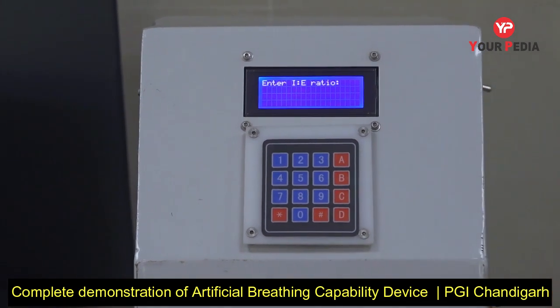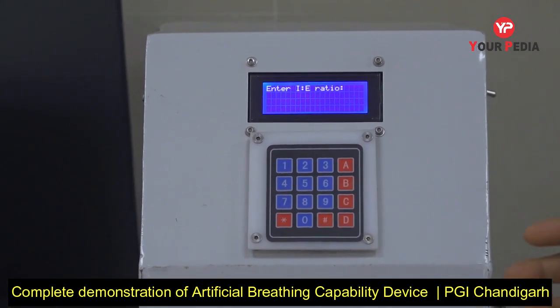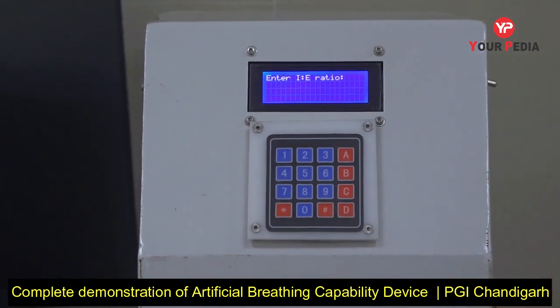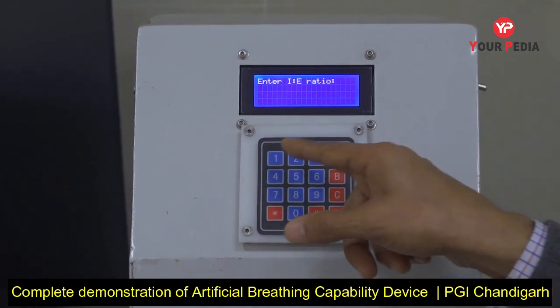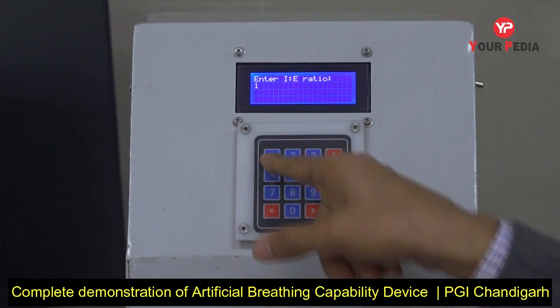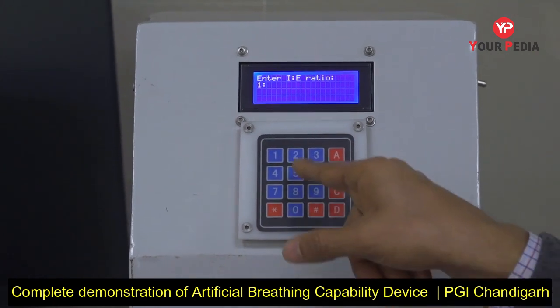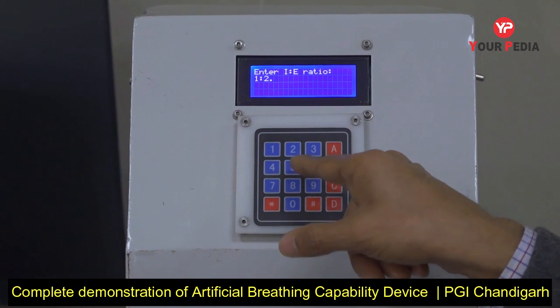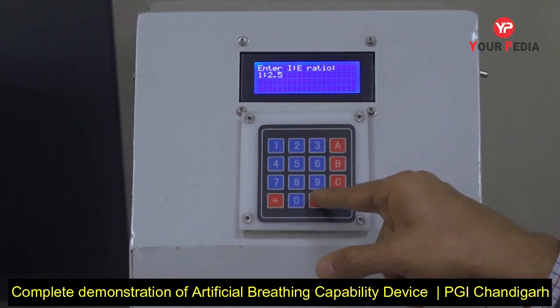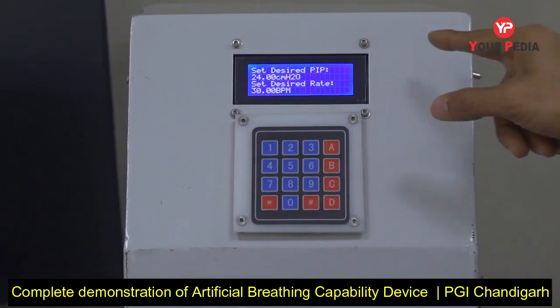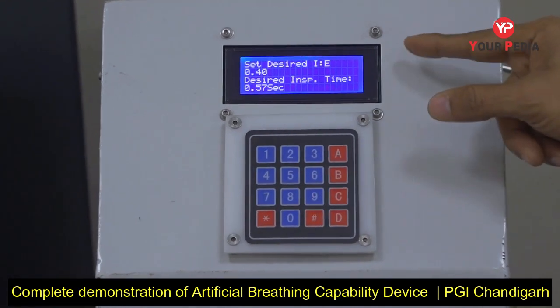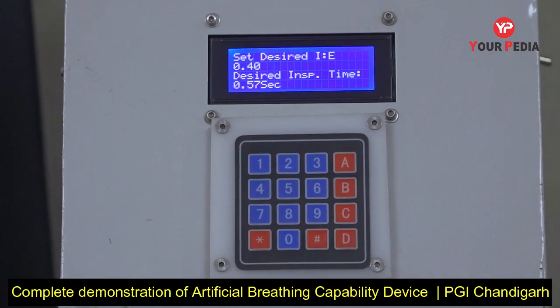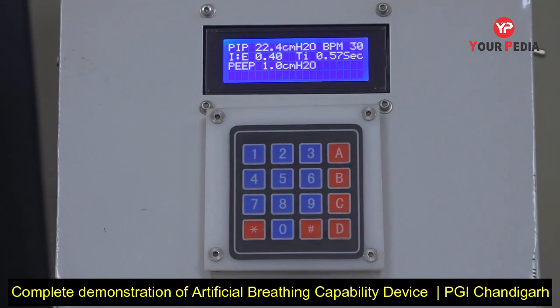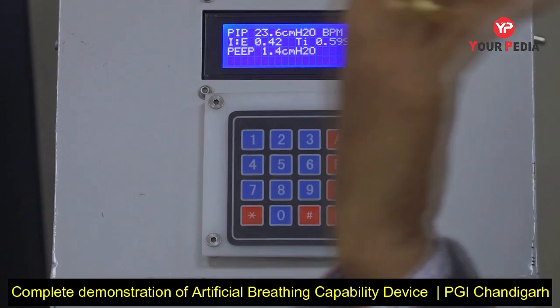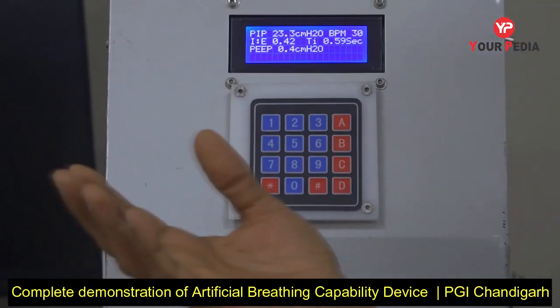The next parameter it asks us to enter is the IE ratio, or the ratio of inspiratory time to expiratory time. So I'm choosing an inspiratory time of, say, 1, and we will select a ratio of 2.5 just to show you the capabilities of this device. Immediately the ventilator shows us the parameters that we have set, and it also calculates the inspiratory time. Thereafter, it immediately starts ventilating and providing the parameters.